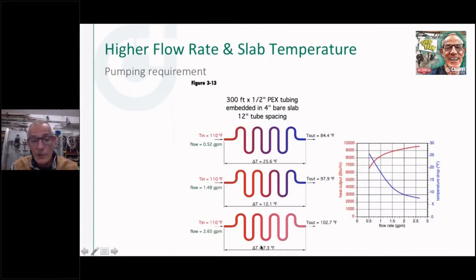I can go all the way down to a 7.3, and now you can see I've got a pretty consistent temperature from the front end to the back end of it. Now keep in mind, it's going to cost you more pumping power to do this, and that's the trade-off: how much circulator do I want to throw at this to get this job done. I'm of the opinion, as long as you're in a low to medium head circulator, that's not too much circulator. If you have to put two double 11 or 2699s, flange to flange together to get this to happen, that's probably not a good design.